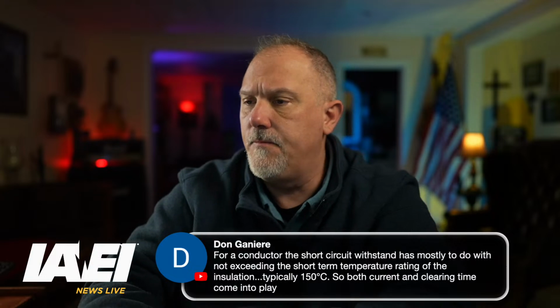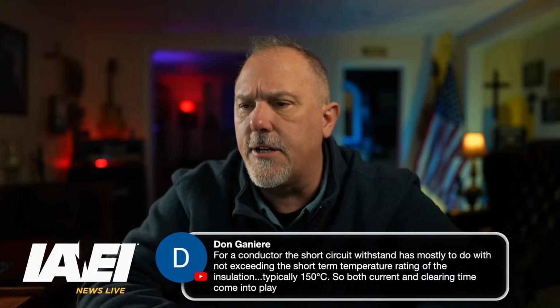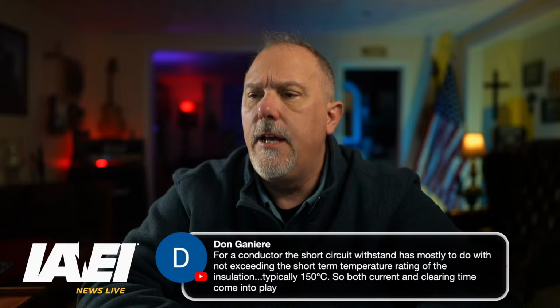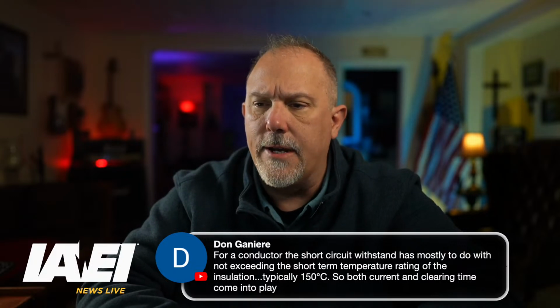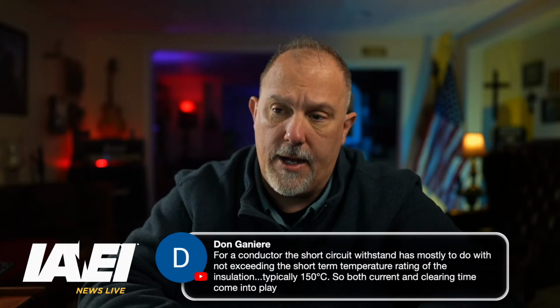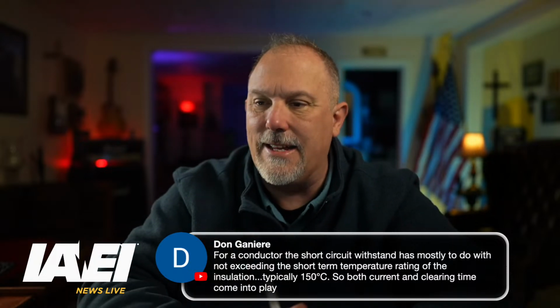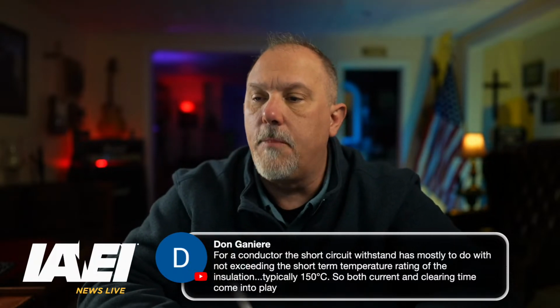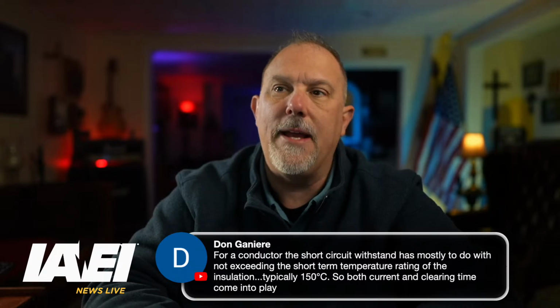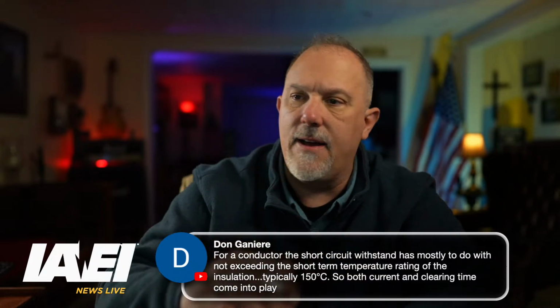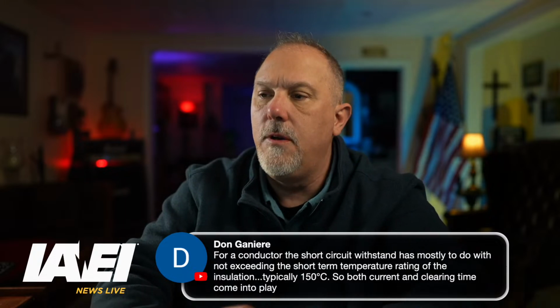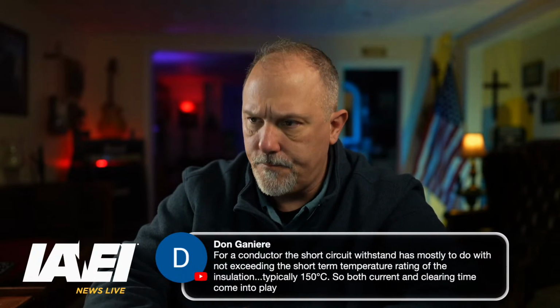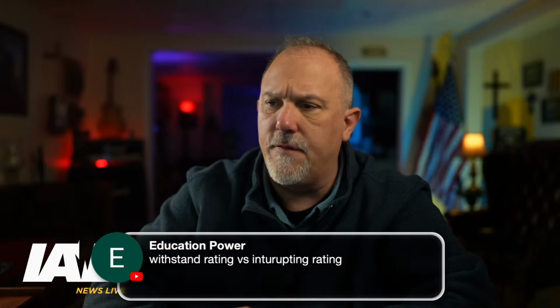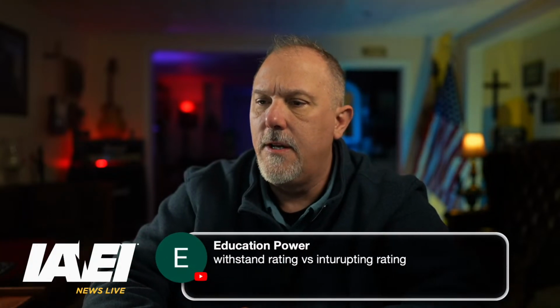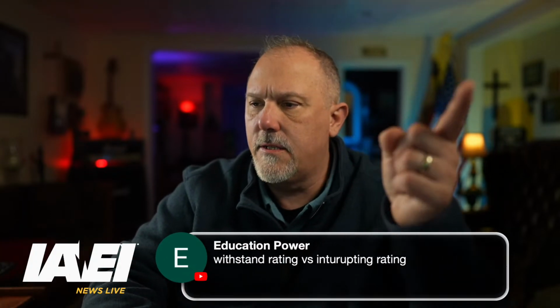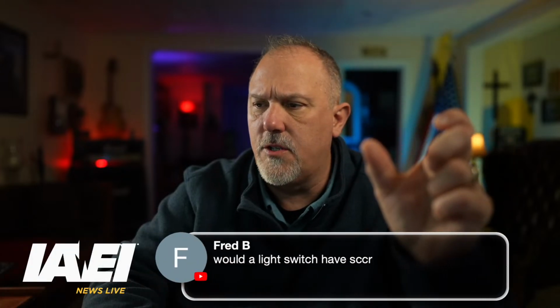Don says, for a conductor, the short circuit withstand has mostly to do with not exceeding the short-term temperature rating of the insulation. Exactly, typically 150 degrees C. So both current and clearing time come into play. Absolutely. The amount of current, the amount of time, and that damage curve that I showed you is based upon the equation that you'll find in the National Electrical Code. Yes, Robert, there's a difference between the two.